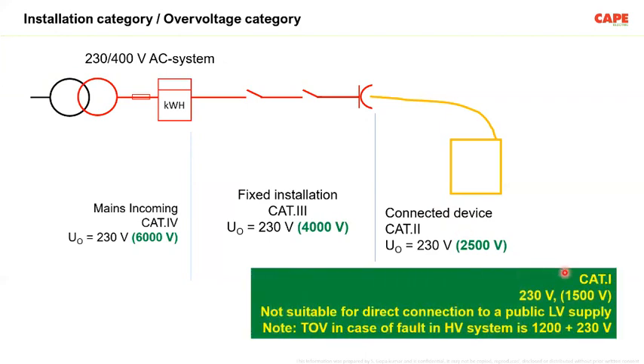Similarly, category 1 devices are also there, meaning a 230 volt device which can withstand only 1500 volt AC and voltage impulse. These devices are actually not suitable for direct connection to a public low voltage supply, because in a public low voltage supply, during a high voltage fault, the energy supplier is free to go to a temporary overvoltage up to 1200 volt plus the operating voltage of 230 volt.